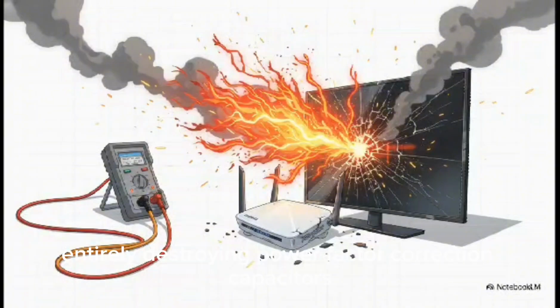I'm talking about entirely destroying power factor correction capacitors, melting electronic light dimmers, and completely frying everyday household items, routers, flat-screen TVs, you name it. You always have to verify you've matched the test voltage to the equipment's actual rating and make absolutely sure those sensitive devices are fully disconnected before you ever press test.